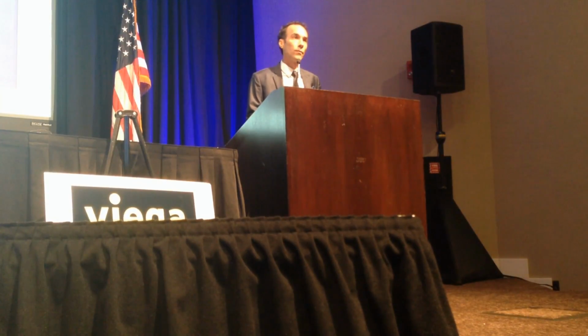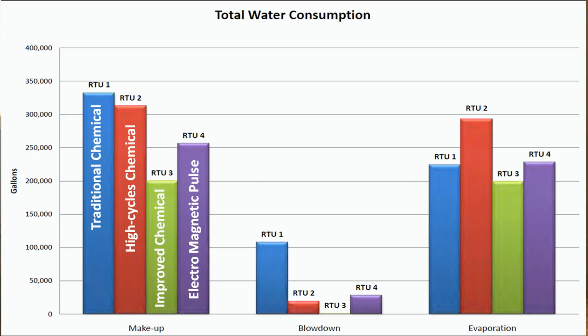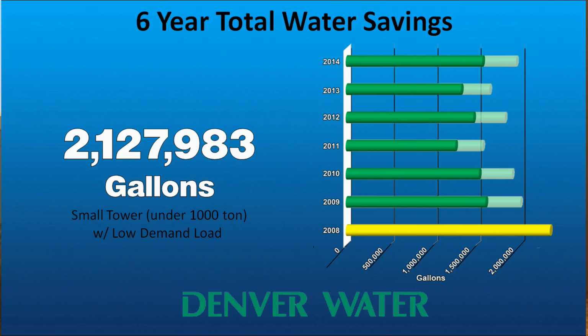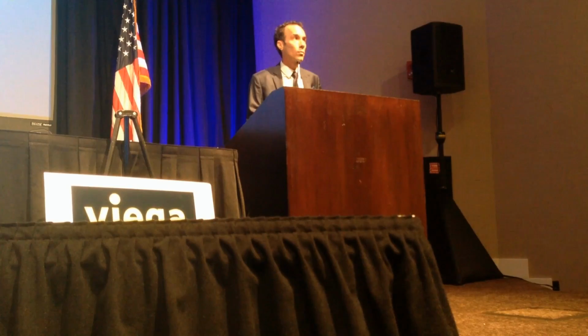And then it came down to this for Denver Water: because they were looking for something that would maintain complete system integrity, provide the highest water conservation, and be economical to implement, the one in green, the improved chemical technology, gave them all three things they were looking for. So I'm happy to say that 6 years and running, it has saved 2.1 million gallons of water. This is a small tower, under 1,000 tons, very low demand. It is in Denver, so the cooling season is short and water costs are low. But Denver Water was quite pleased with it, and the technology remains on the building.